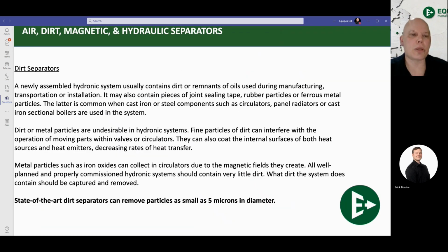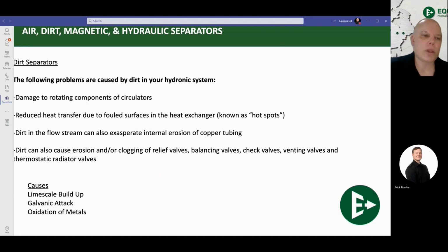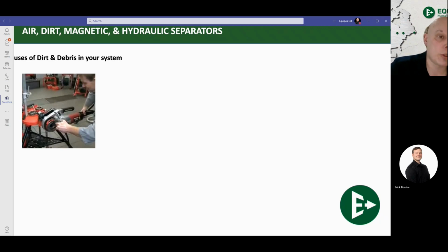Dirt separators are the pieces that are going to remove your little bits of dirt, your flux, your solder, your Teflon tape, your buildup of little bits of lime and calcium scale that builds up inside of a system, any dirt or sand or anything like that that creates inside of a system. This is where that comes out, on the inside of a dirt separator. Now, dirt separators are usually put on the last thing back to the boilers, the last thing that it sees. It's a good idea for your dirt separators to use something that can be flushed, where something like a Y strainer has to be taken apart and cleaned. Flushing is much, much simpler and much easier to do inside your system.